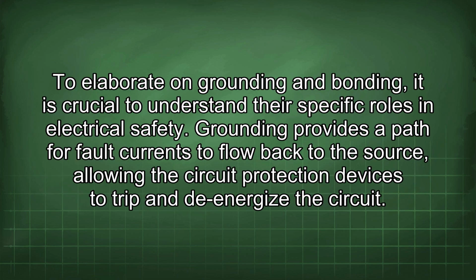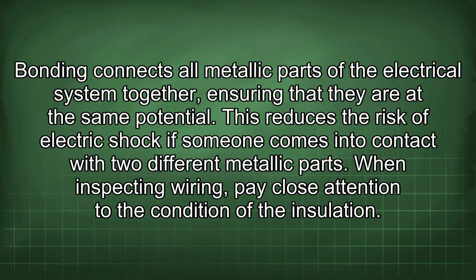To elaborate on grounding and bonding, it is crucial to understand their specific roles in electrical safety. Grounding provides a path for fault currents to flow back to the source, allowing the circuit protection devices to trip and de-energize the circuit. Bonding connects all metallic parts of the electrical system together, ensuring that they are at the same potential. This reduces the risk of electric shock if someone comes into contact with two different metallic parts.